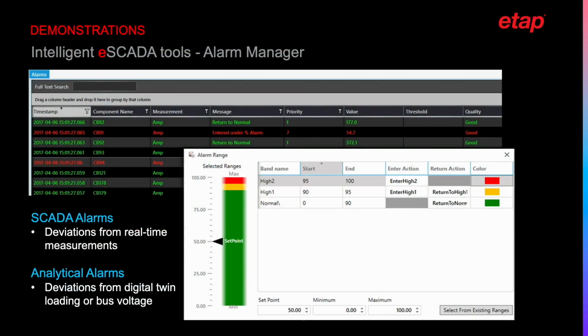Next, we can look at some of the additional benefits of the intelligent SCADA tools. The ETAP Alarm Manager allows the operator to look at different types of alarms, including SCADA alarms and analytical alarms. SCADA alarms are caused by deviations from real-time measurements to an undesired range of operating state. Analytical alarms are generated by ETAP because of detecting deviations in the operating loading or bus voltage in the digital twin model using real-time conditions.